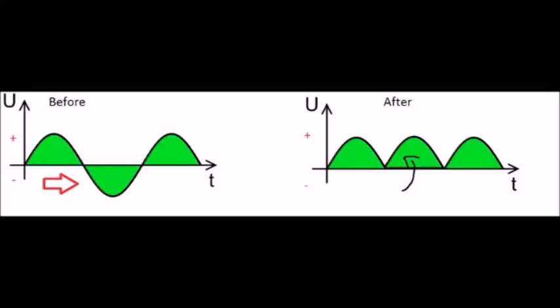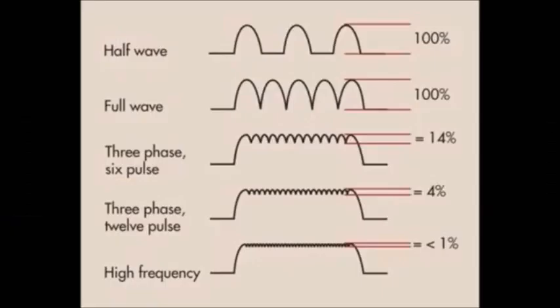Full-wave rectification reverses the negative half cycle so that the anode is always positive; the exposure time for a given technique is cut in half. Although full-wave is a step up in efficiency, it still contains 100% voltage ripple, where voltage gets down to zero at times.